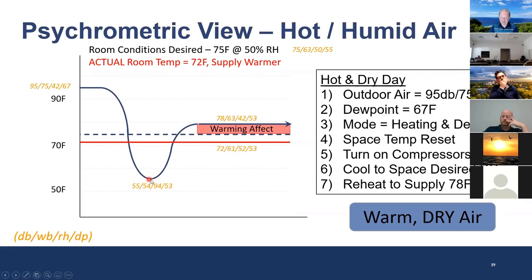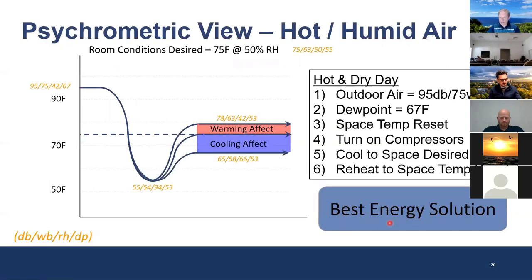You might even be able to do a reset on the leaving coil temperature — raising it if you don't need as much dehumidification for even more energy efficiency savings. For today's purposes, I basically set the coil suction temperature targeting 55°F leaving air. One question that comes up is how to measure and where sensors go. Taking the hot air and cooling it below the desired dew point, then with DX heating and dehumidification, we can still deliver warm and dry air.